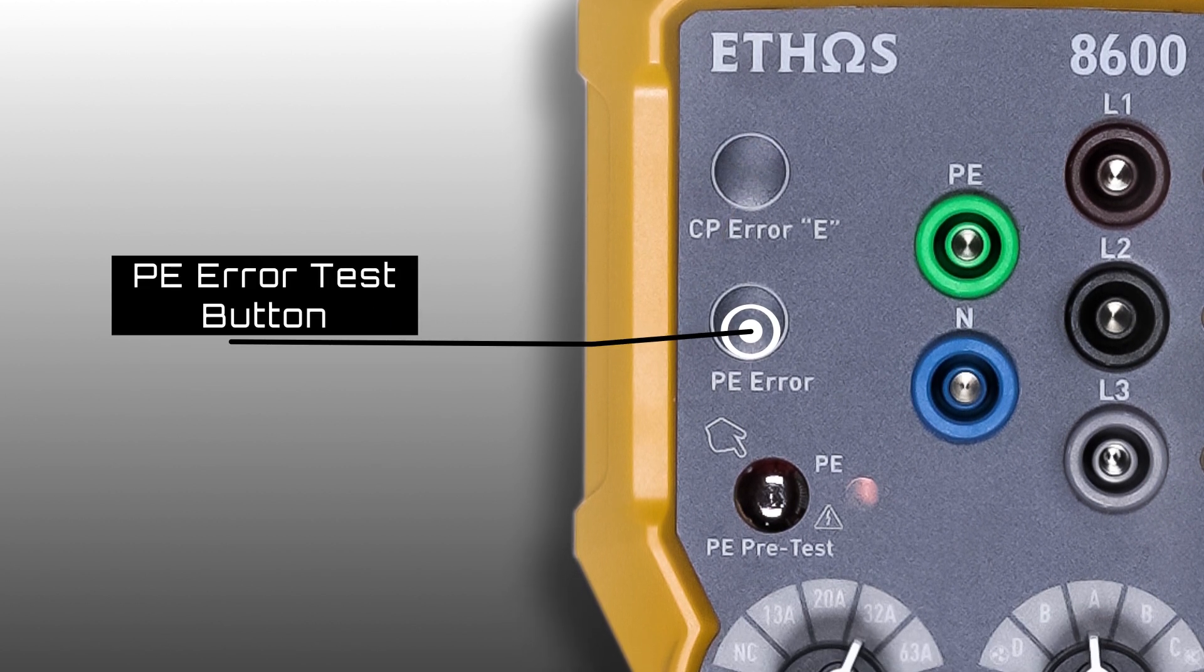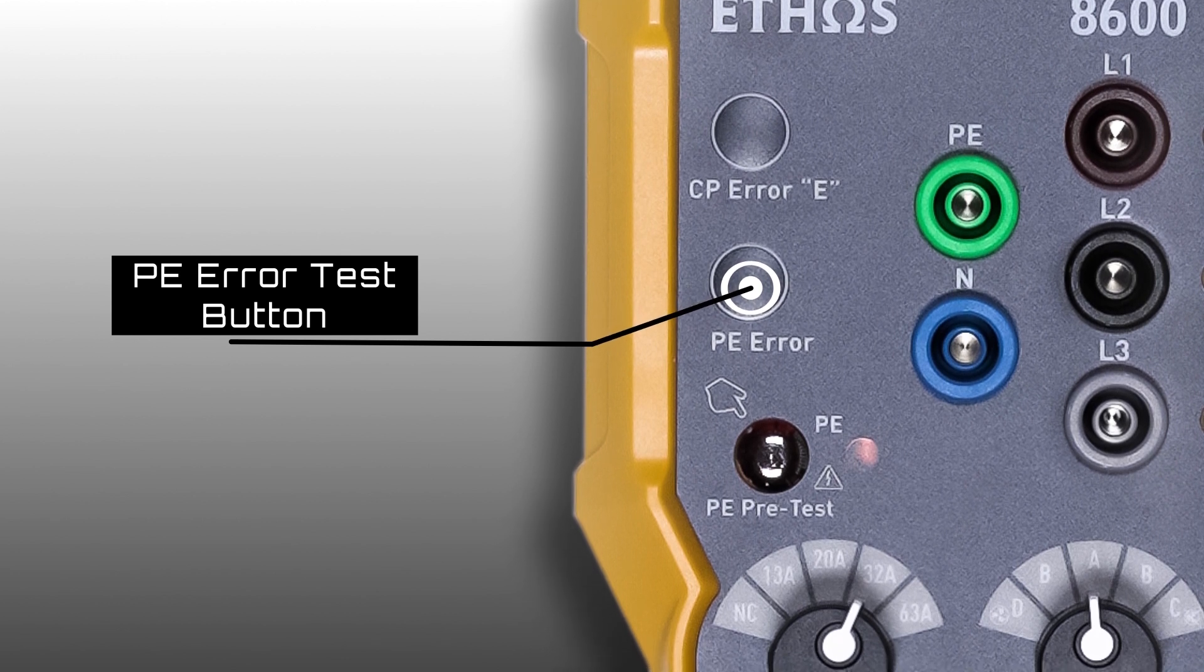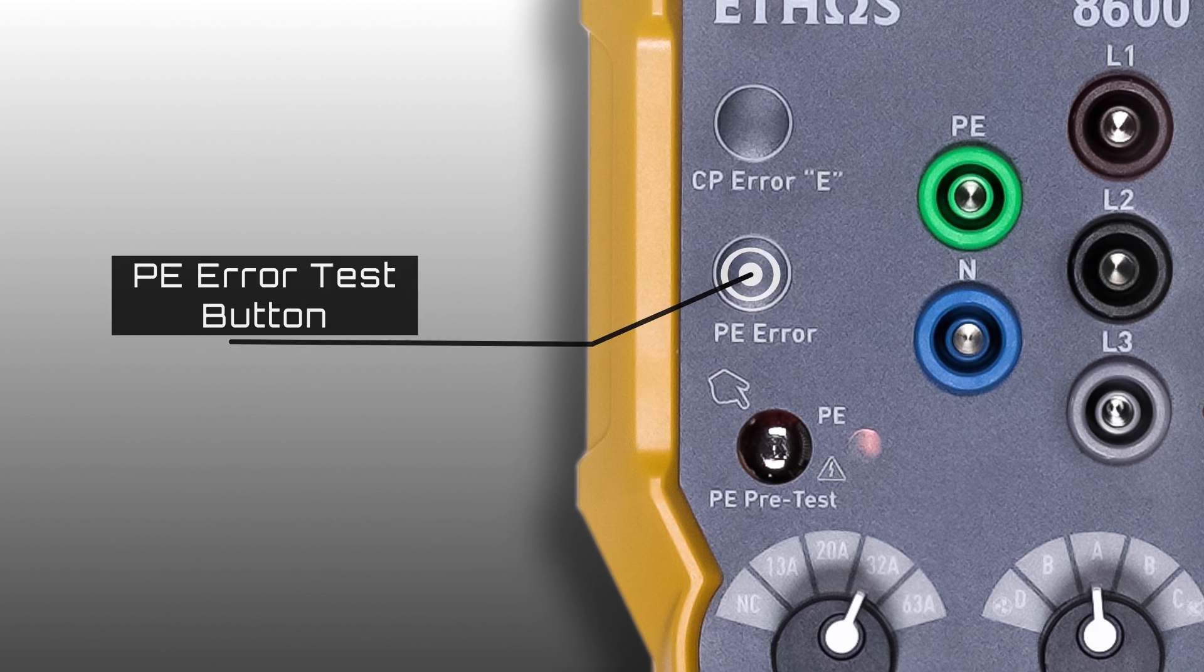PE error test button. This is pressed to simulate a fault on the earth conductor. The charge point will shut down confirming the safety process is working correctly.